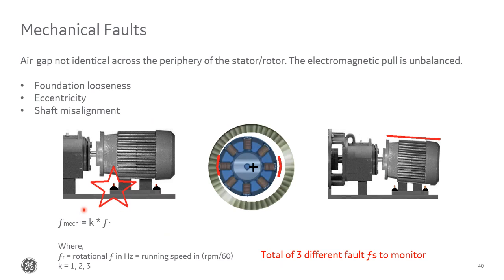In terms of the formula for the frequency calculation here, this is a big one that we changed. Looks pretty simple here. But the old calculation used to take into account the slip of the motor, which poses a challenge for synchronous motors since the slip is 0, and also the number of poles. Again, with this new signal shift that we do, we've simplified this greatly, and we can find these faults basically at the motor's rotational frequency. And then again, 3 harmonics of it. So where we used to need to look at 6 frequencies, now we're only looking at 3 frequencies. And because we don't use the slip, we also support synchronous motors now, which I'll talk about a little bit later.